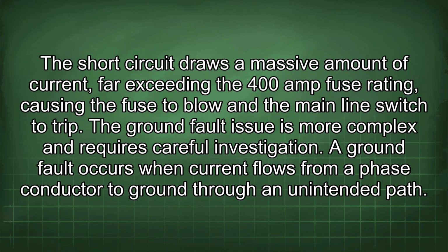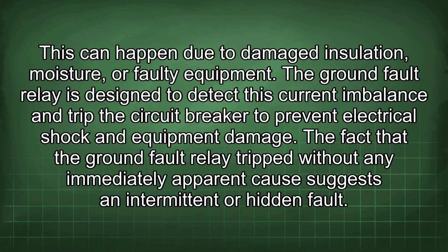The short circuit draws a massive amount of current, far exceeding the 400 amp fuse rating, causing the fuse to blow and the main line switch to trip. The ground fault issue is more complex and requires careful investigation. A ground fault occurs when current flows from a phase conductor to ground through an unintended path. This can happen due to damaged insulation, moisture, or faulty equipment.